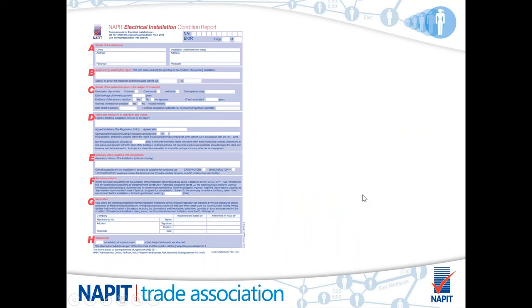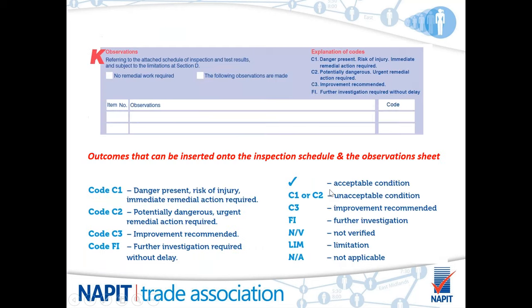Obviously, NAPIT have their forms that we use based on the documentation in Appendix 6 of the regulations. Our electrical installation condition report is the one that is used, obviously, for periodic inspection and testing of all installations. The EICR observation sheet is used to record any defects within the installation. These observations should then be assigned the appropriate code.